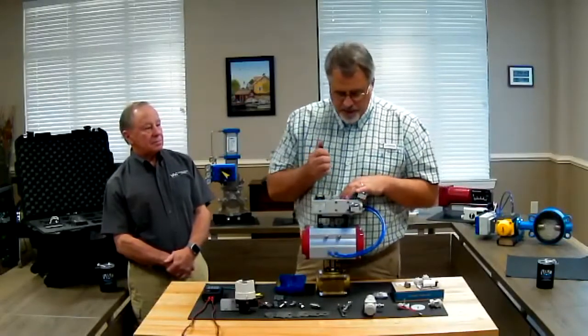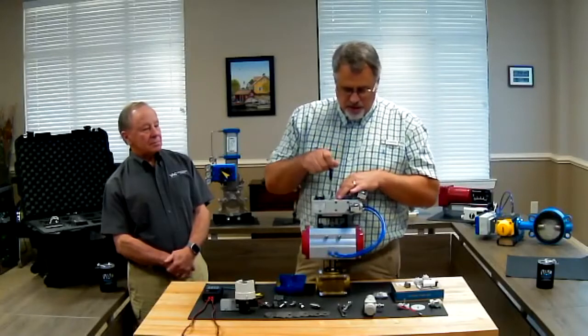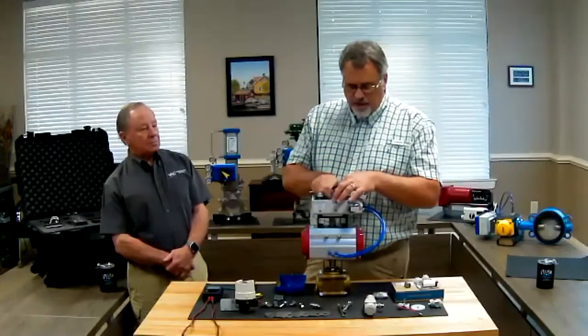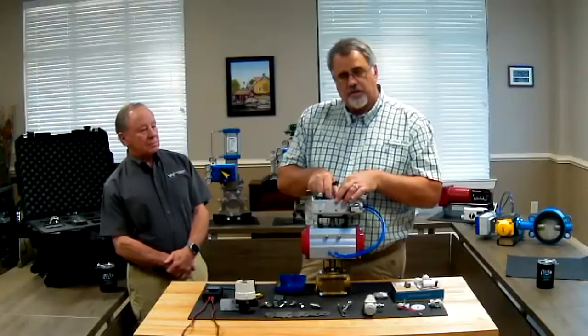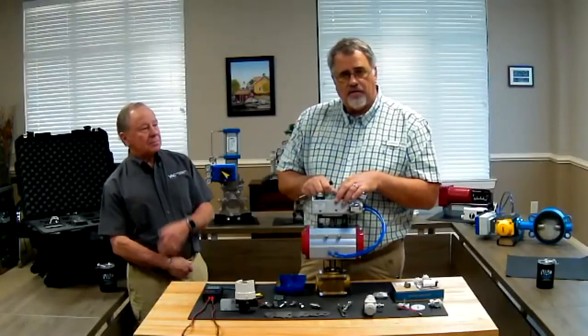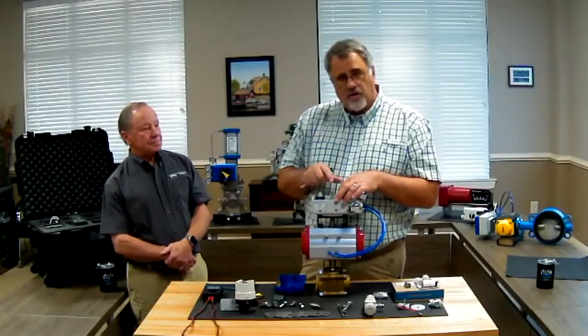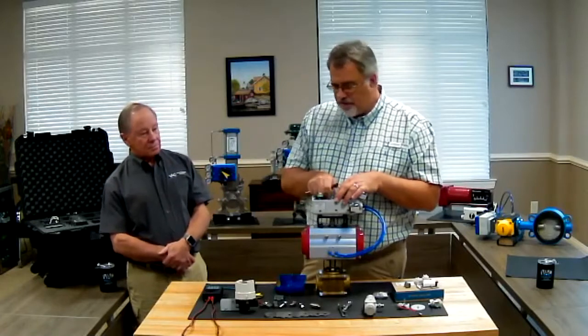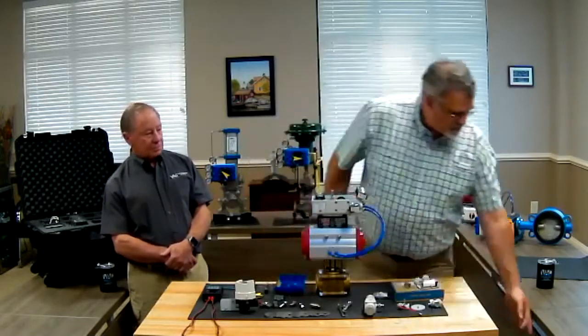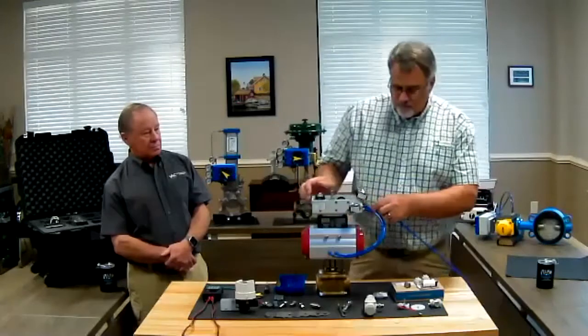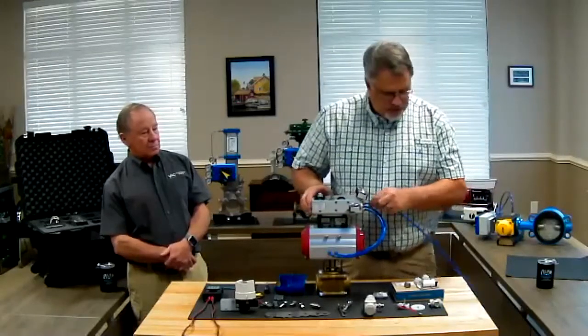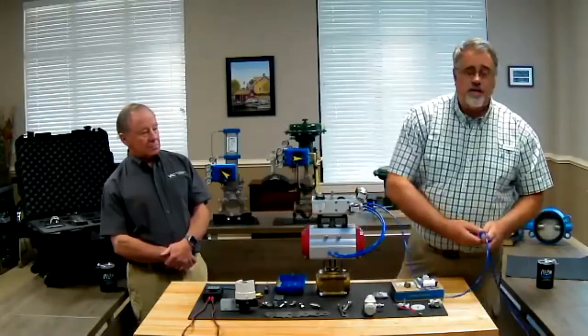The first step in calibrating the positioner is I'm going to loosen a locking screw here, my cam nut, and set my cam so there's a small gap. There's a video on the YouTube channel showing all of these steps. Okay, and once I've got that gap set, I'm going to air this positioner up and confirm that mechanically it's correct.